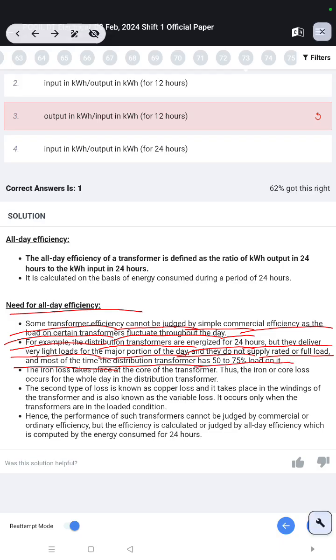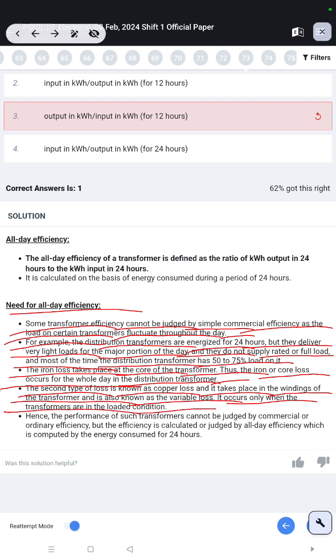The iron loss takes place at the core of the transformer, thus the iron or core loss occurs for the whole day in the distribution transformers. The second type of loss is known as copper loss and it takes place in the windings of the transformer and is also known as the variable loss. It occurs only when transformers are in loaded condition. Hence, the performance of such transformers cannot be judged by commercial or ordinary efficiency, but the efficiency is calculated or judged by all day efficiency, which is computed by the energy consumed for 24 hours.